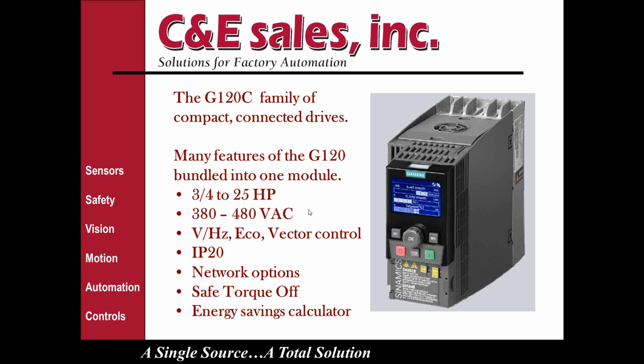It is an IP20, so it is intended to be mounted inside an enclosure, like the other drives we've talked about so far. It comes with safe torque off, but does not have the extended safety functions available. So if you do need the extended safety functions, you need to go to a G120. And it does have a nice little built-in energy savings calculator that you can use.